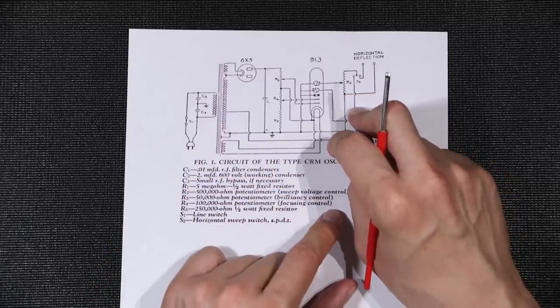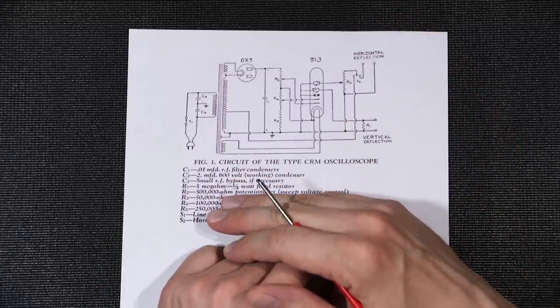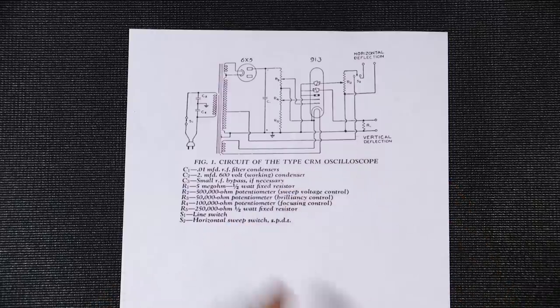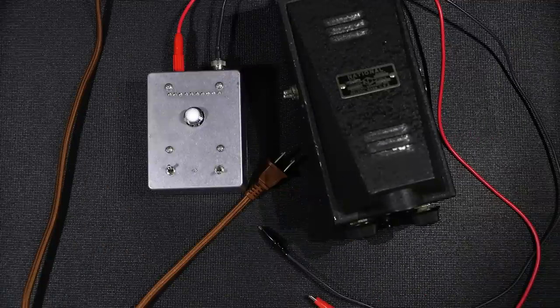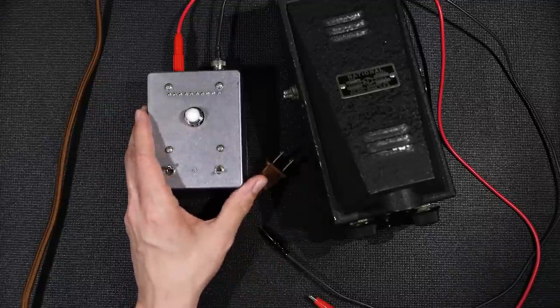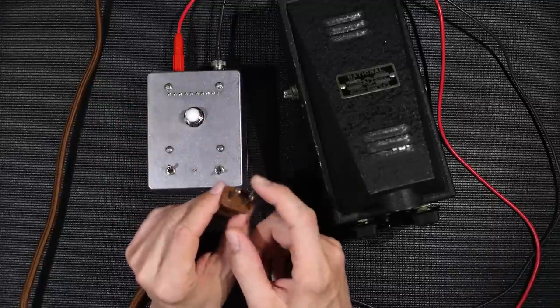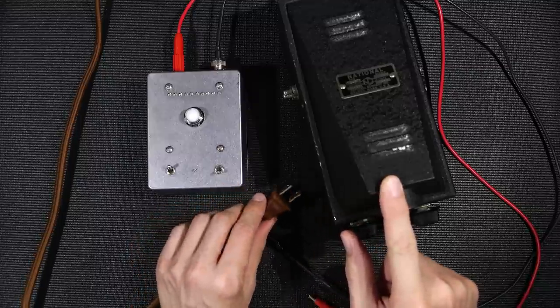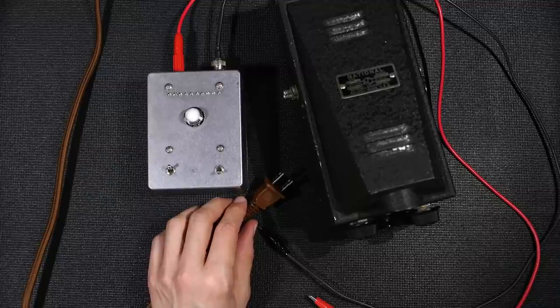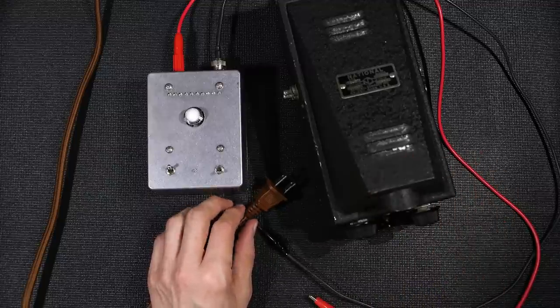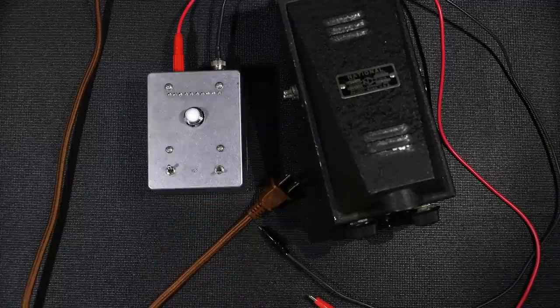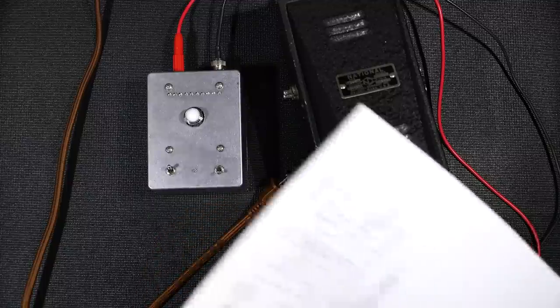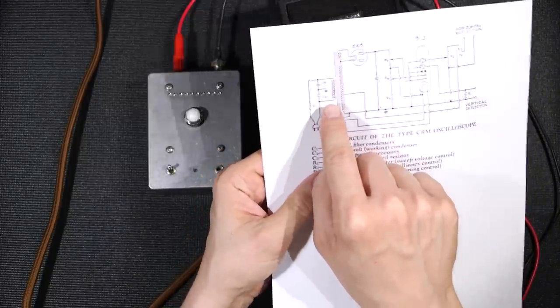So let's take a look and see if those capacitors are hiding in this transformer. I'm going to use the leakage tester to check whether there's any capacitor from either side of the line cord to the chassis of this scope. If there is, that's going to present some form of leakage to the chassis, making this a shock hazard. If they're in there, either the transformer will have to be changed or it will have to be depotted.